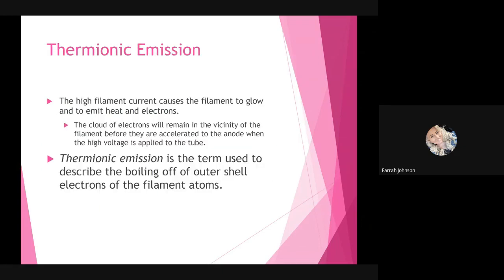So once again, thermionic emission. The high filament current is going to cause the filament to glow and to emit heat and electrons. That is the process of thermionic emission. Now that cloud of electrons will remain in the vicinity of the filament before they are accelerated to the anode when the high voltage is applied to the tube. Okay, so once that high voltage is applied to the tube, it is going to accelerate that thermionic emission cloud of electrons over to the anode for X-ray interaction. Now, thermionic emission is the term used to describe the boiling off of outer shell electrons of the filament atoms.